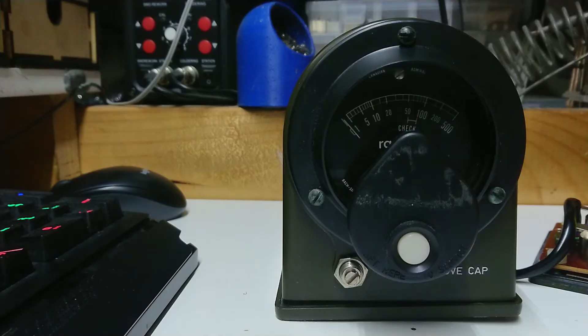Alright, I've got a little bit of backlighting here to help. I've actually calibrated this till it sits on the 1 just to make it a little easier to see. Now, it's at a funny angle because I've taken the ionization chamber out and it's sitting on the bench. Because I'm trying to sit these thoriated rods really anywhere as close as I can to the chamber to see if I can influence it even in the slightest. Which, with this test source, I'm probably not going to be able to. So yeah, I do have some americium, but it doesn't put out a lot of gamma particles. I might try a bit of uranium glass and see what happens.